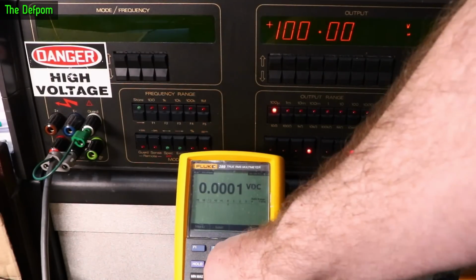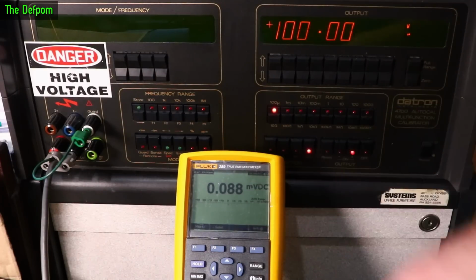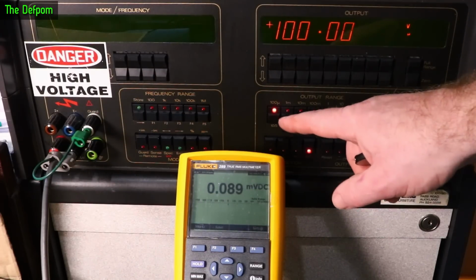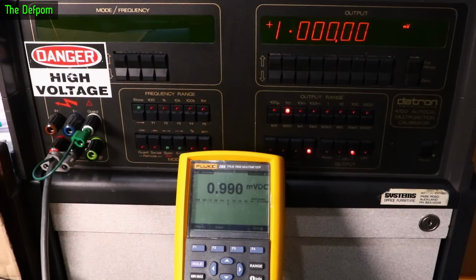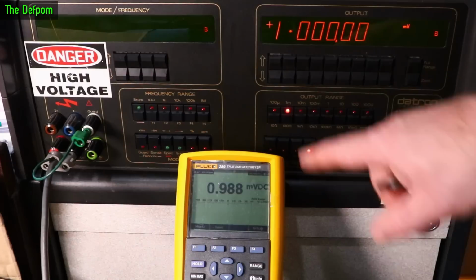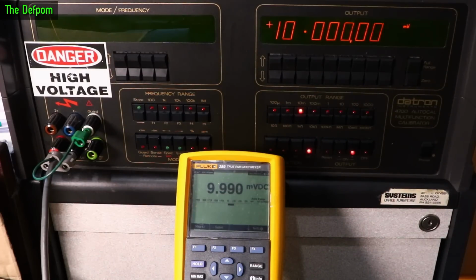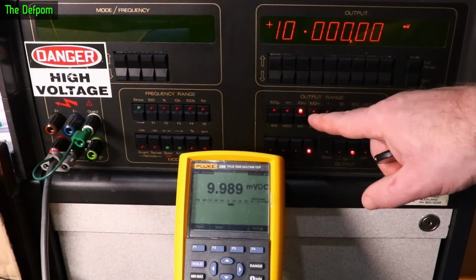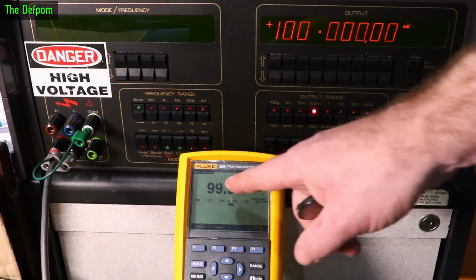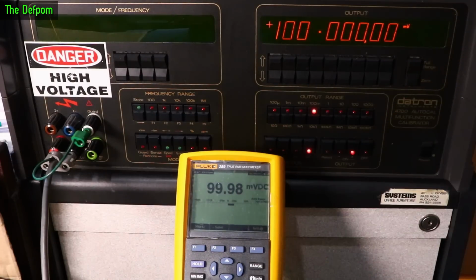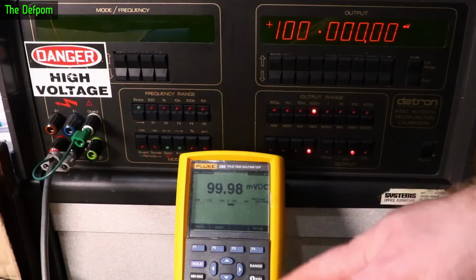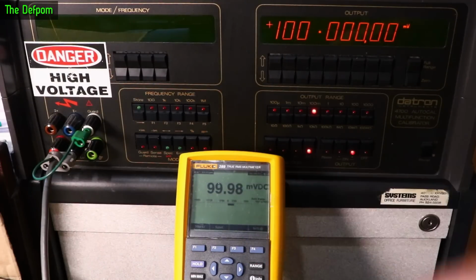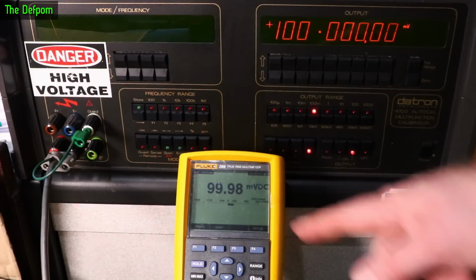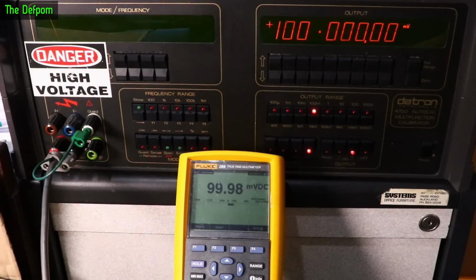So let's do the millivolt range now. We're down here. Yeah, so 100 microvolts is showing up as 88. Okay. Bit out there. 1 millivolt is reading as 0.98. Don't forget on the volts range it was perfect. So we've got a bit of a discrepancy there between those ranges. So 10 millivolts is also reading 9.98. A couple of counts down, or I suppose you can say 1 count down really. And 100 millivolts is 99.98. So this is reading down by a couple of counts on the millivolt range. Volt range, as you saw, was looking really good, but millivolts is slightly out. I'm surprised. It's not out by much. I'm sure it's well within spec. It would have been nice to be a bit more precise than that.